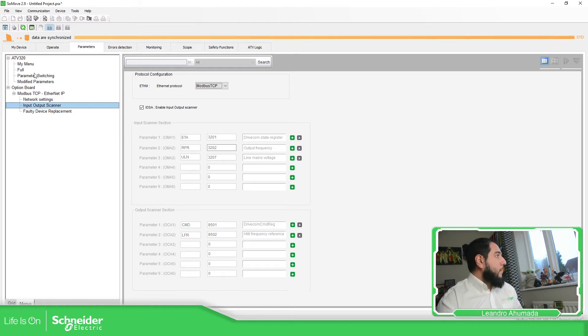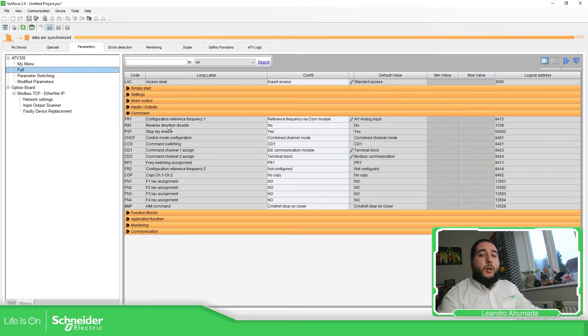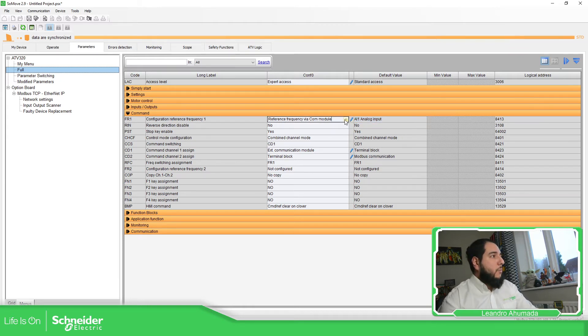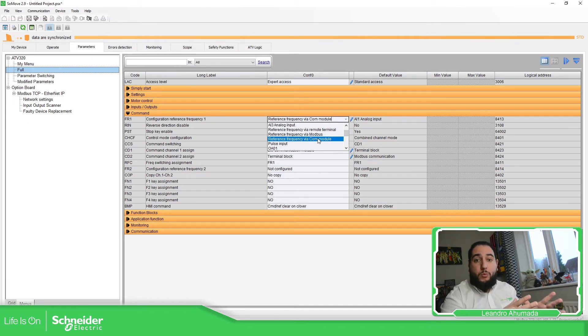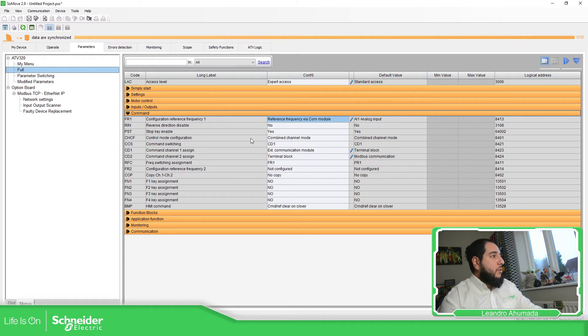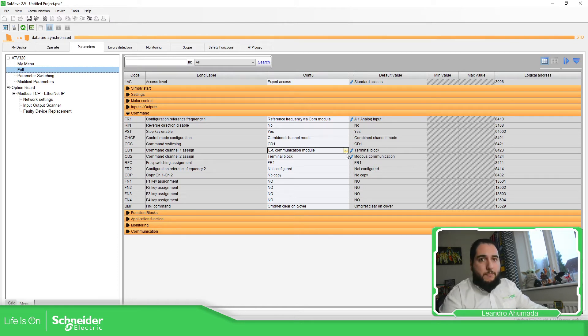What we need to change is everything to communication, if we want the drive to be controlled from the communication side. Let me check here in commands — in commands, you can see that by default it is set to analog input, and I want it to be the communication card. I have selected the communication module, which is the one added to the bottom of the drive. Then we need to select the combine channel, and in my case I use the external communication module — it came from communication, just with different short names, but it's the same.